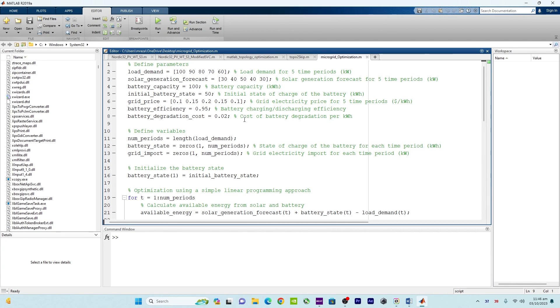The battery degradation cost is considered to be a constant value of $0.02 per kilowatt-hour. This means that for every kilowatt-hour of energy that passes through the battery — whether charged or discharged — there is a cost of $0.02 associated with battery degradation. This is a simplified assumption for the sake of illustration and ease of understanding.